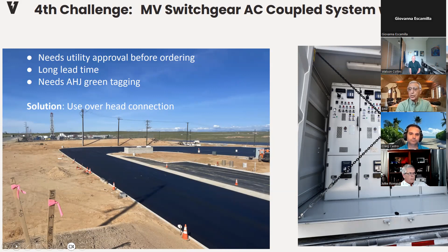This shows the recloser that, with PG&E's guidance, we were able to secure to achieve the medium voltage interface. The meter is installed directly on the pole, allowing us to run behind-the-meter medium voltage lines through the property all the way to the chargers.